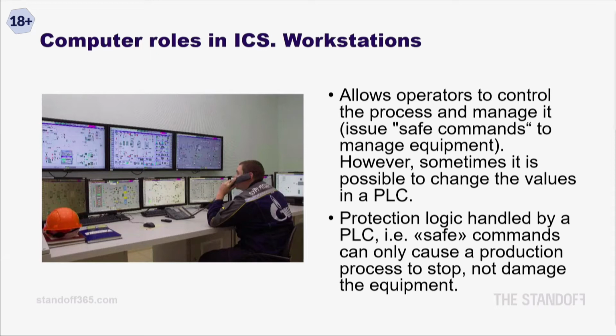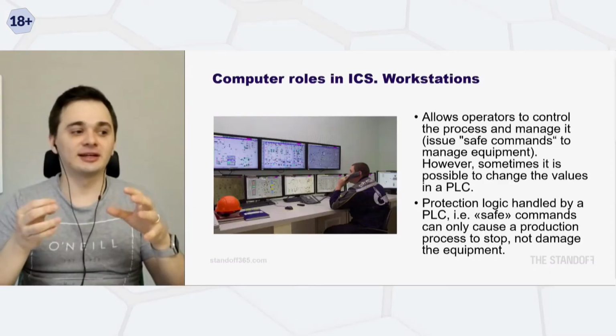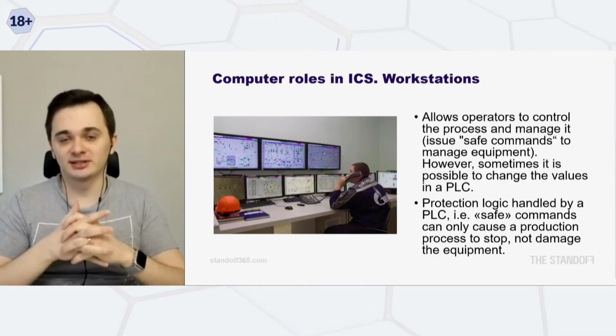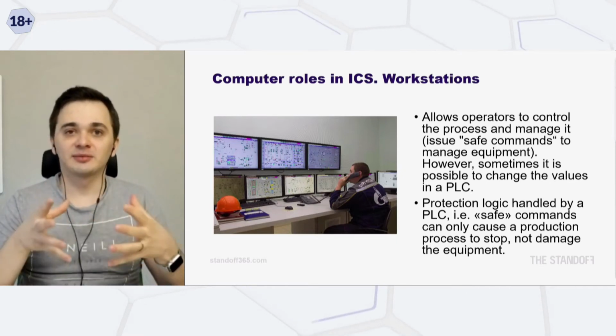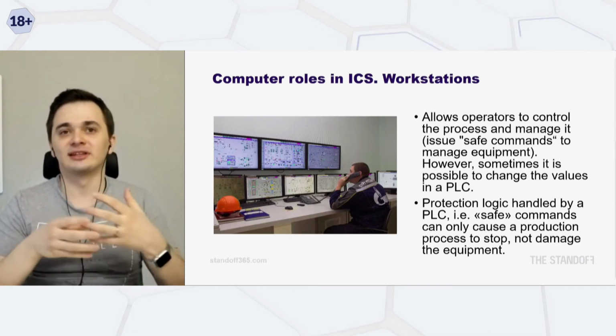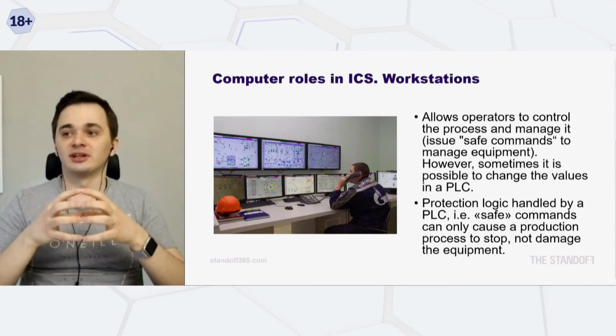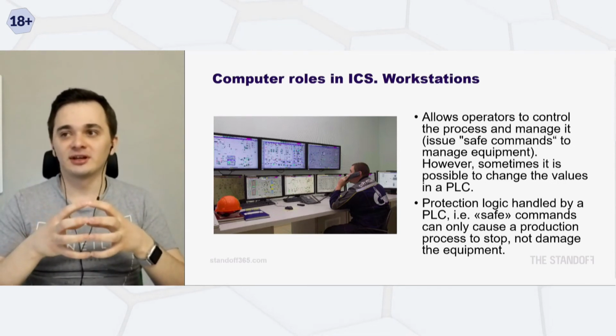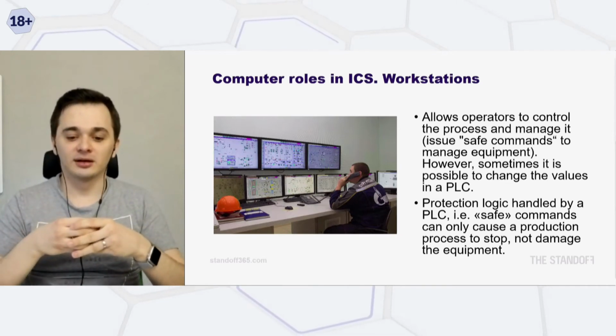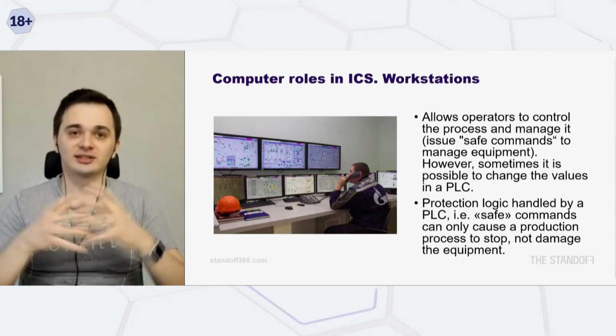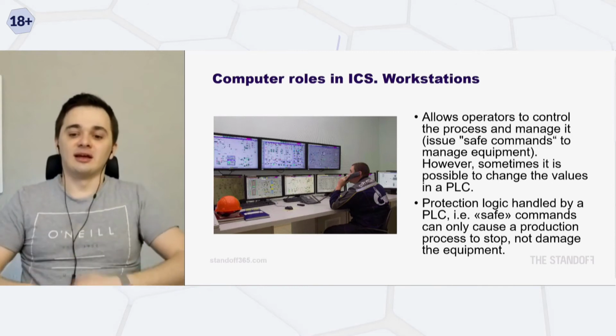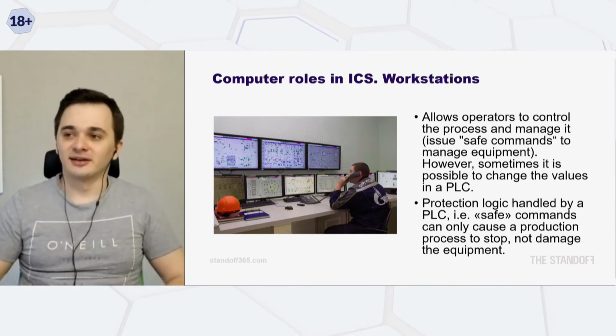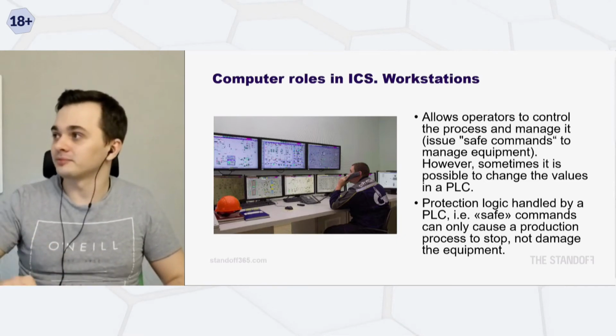This logic can be maintained in a single PLC, or alternatively it can be done at the stack level on the main PLC. In certain assets, such as nuclear power plants, you will see the so-called 2 out of 3 system, where you have 3 PLCs, and before anything is done, they need to negotiate if data coming from 2 PLCs is the same. Then the action is vetted and given a green light. So this is another layer of redundancy, you may argue, but it's also a layer of protection.